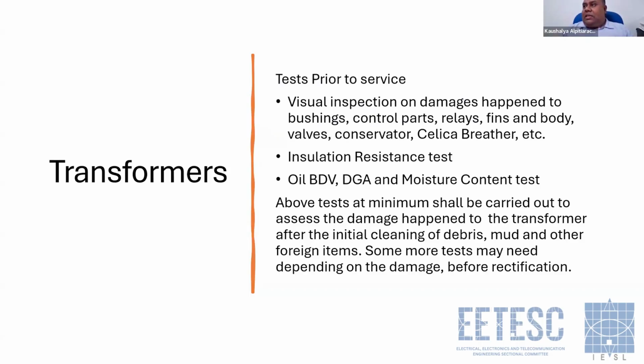First, conduct an insulation resistance test and see what the damage is and what has happened. Then an oil BDV test. If it was in operation when the flood happened, a DGA test and a moisture content test. This is enough for you to get an idea of what has happened to the transformer, what's inside the transformer, and what level of action is required.